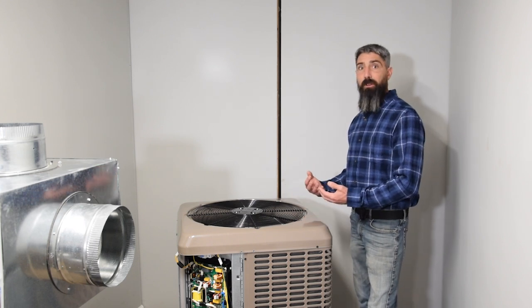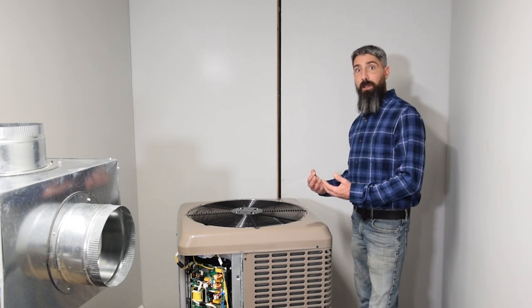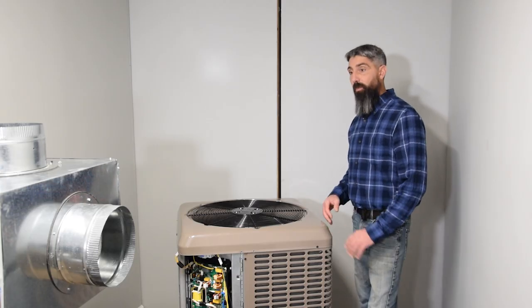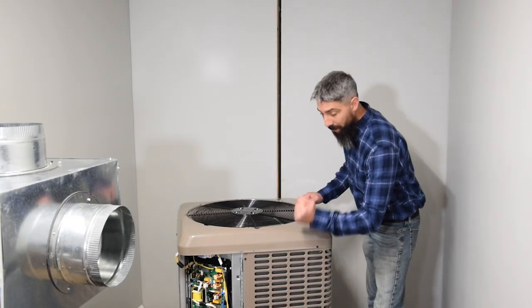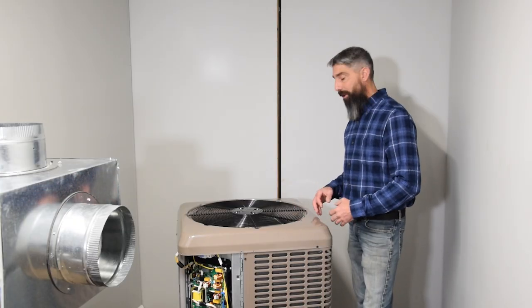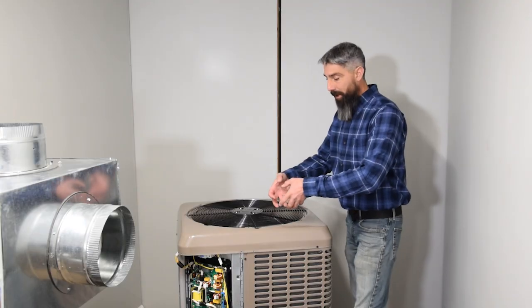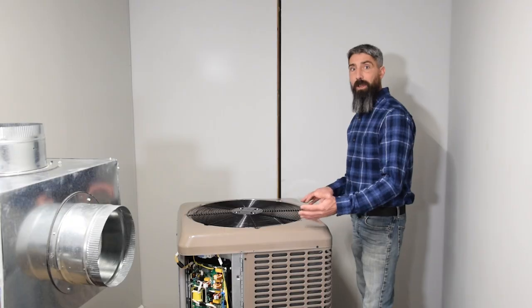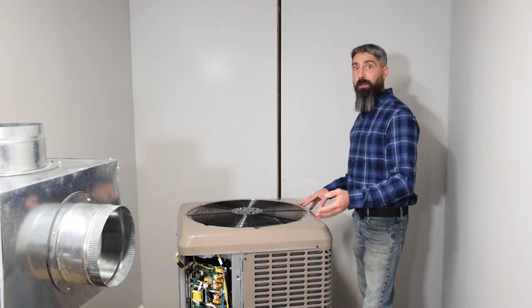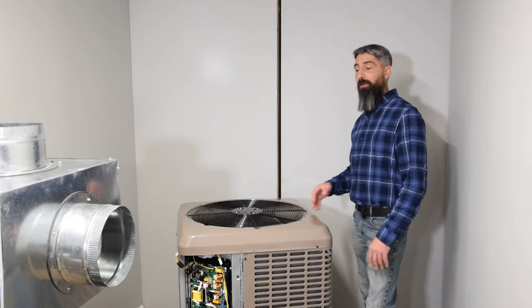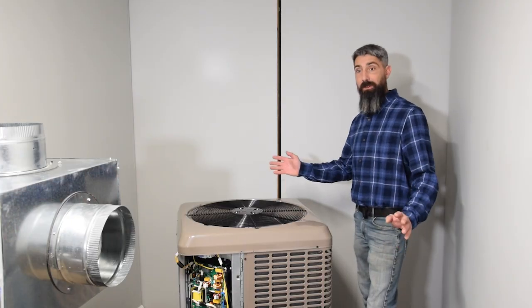So to manually do it, that's the most delicate way I can find to defrost the system. We never use any objects or any force actions trying to come down on the ice to try to break up that ice because it's wrapped up around the capillary tubes on side of the condensing unit. You got the chance of having a screwdriver stab through your coil, anything like that. Now you just bust your unit up.